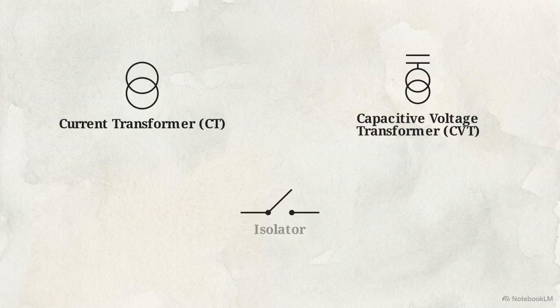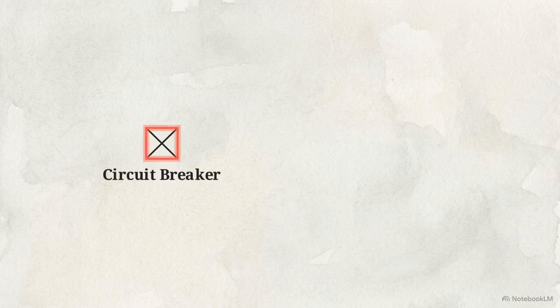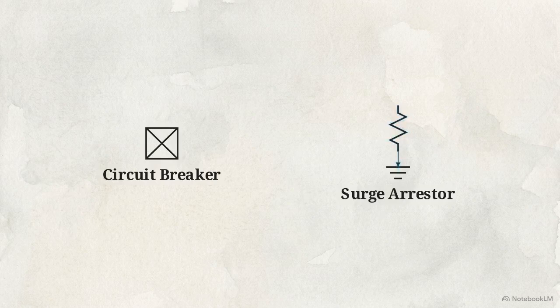Key components include current transformers, capacitive voltage transformers, and isolators, which manage and measure the flow of electricity. Two critical defensive components are the circuit breaker, which physically opens to interrupt dangerous fault currents, and the surge arrestor, which bleeds off extreme voltage spikes before they can damage adjacent equipment.